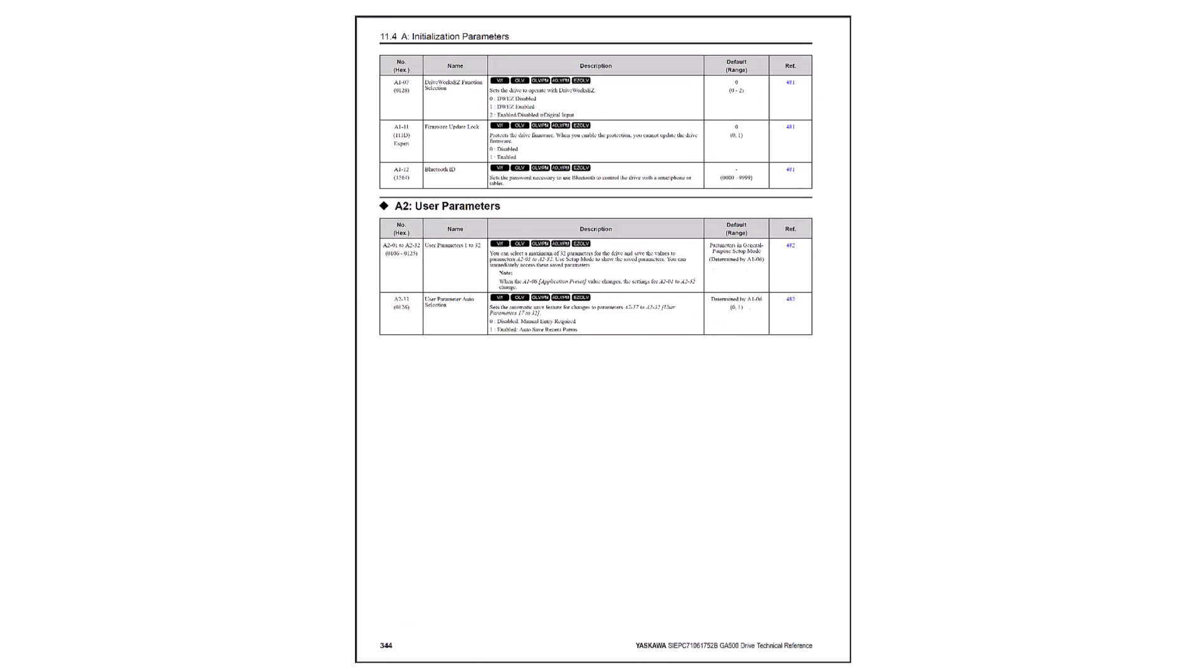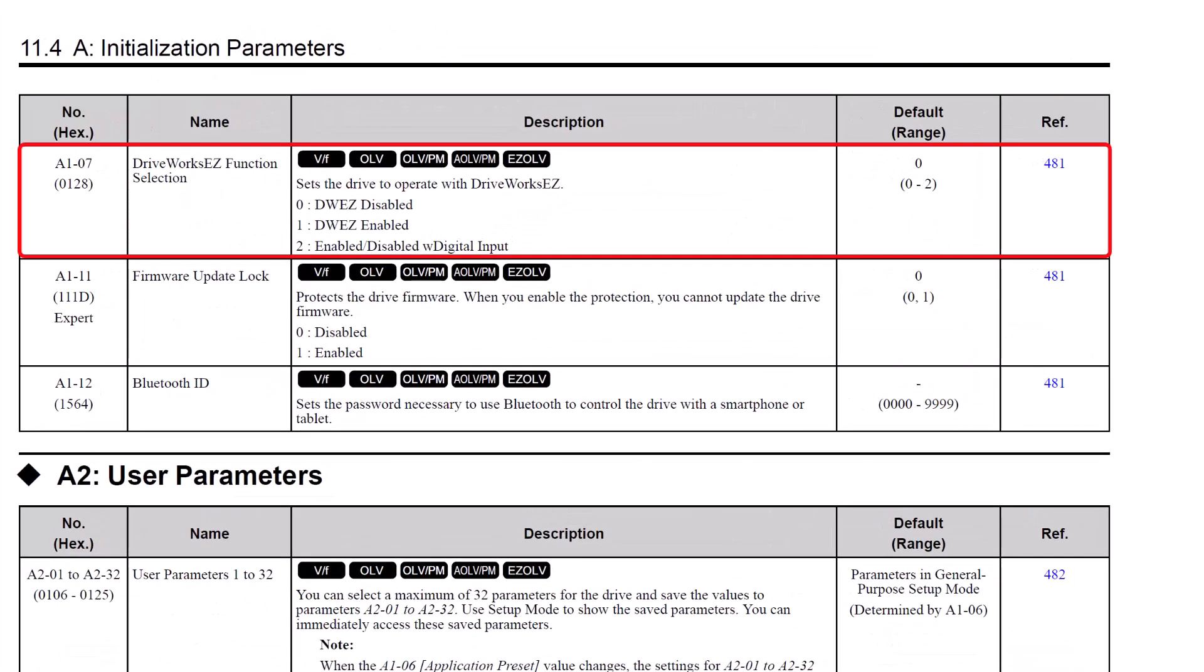Parameter A1-07 is how this is done. By default, A1-07 is equal to 0, disabled, meaning there could be a DriveWorks EZ program loaded into the drive, but it is not active since it is disabled. You can enable DriveWorks EZ by setting this to 1.